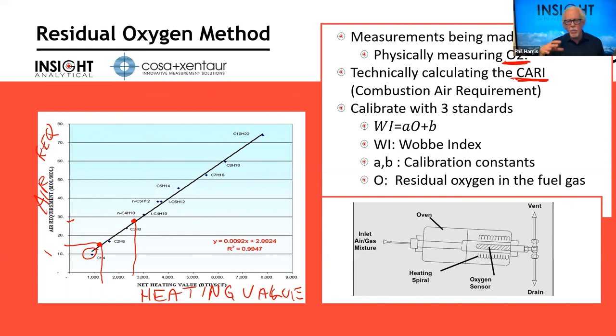We build a calibration model around three specific standards: the low-end BTU of what we think the fuel is going to look like, the high-end BTU of what we think the fuel is going to look like, and one in the middle. And we build calibration constants from that that let us calibrate the Wobbe Index. So from the measurement of oxygen, we get to figure out how much air I have to put in my burner, and that's the thing I want to know. If I can run my burner with the optimum air to fuel ratio all the time, I'm getting the maximum energy out of my fuel. I'm not wasting any energy by heating too much air, I'm not wasting any energy by leaving unburned fuel there, and I'm reducing my environmental emissions.